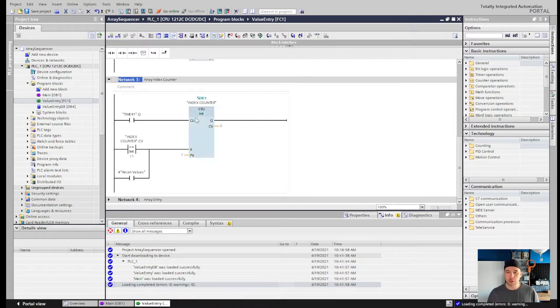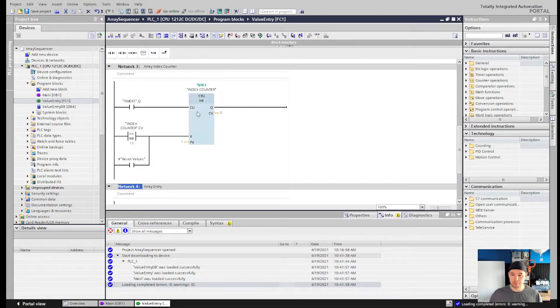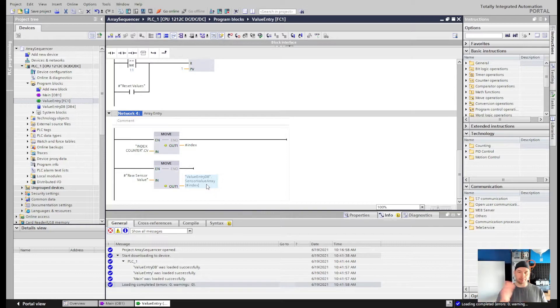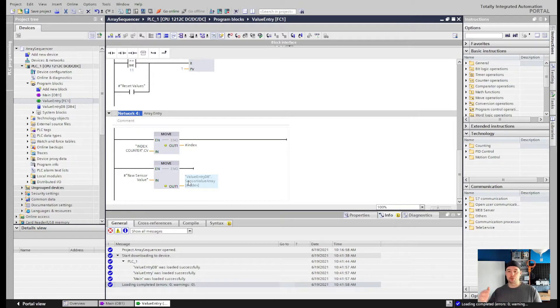The array entry network is the important one. The count value increments and I push it into a temporary index tag — just an INT tag storing the current position. In the next move instruction I take the raw sensor value and move it into the Value Entry data block sensor value array, but instead of a fixed address like zero, one, or two, I pass this index tag dynamically. So as the index tag increments from zero to eleven, the data gets pushed into each successive array position in sequence.